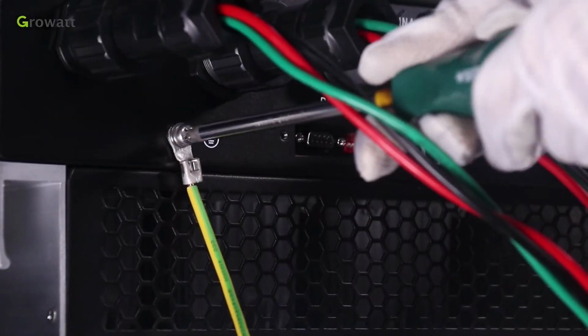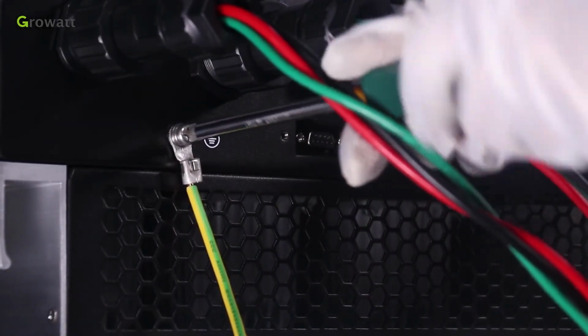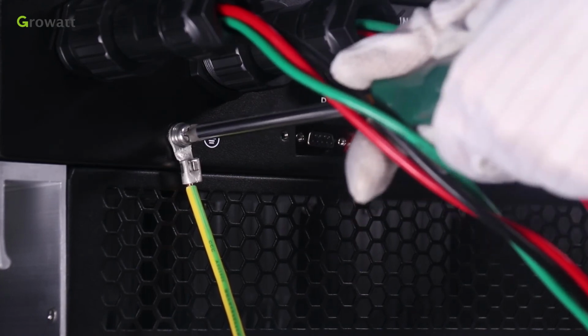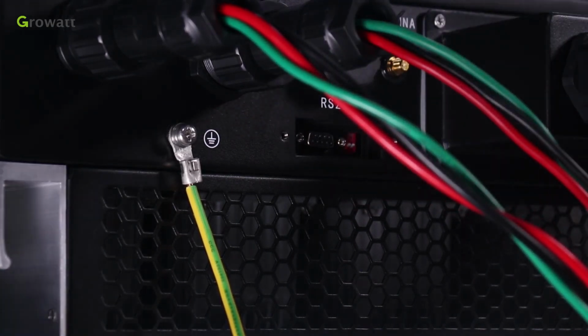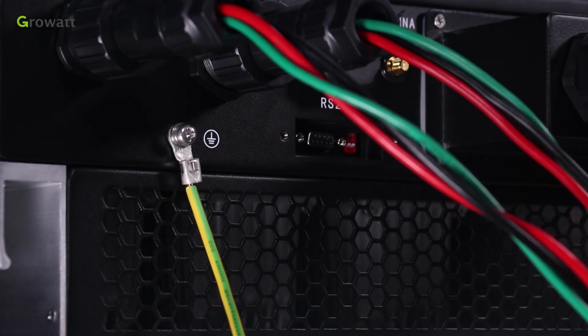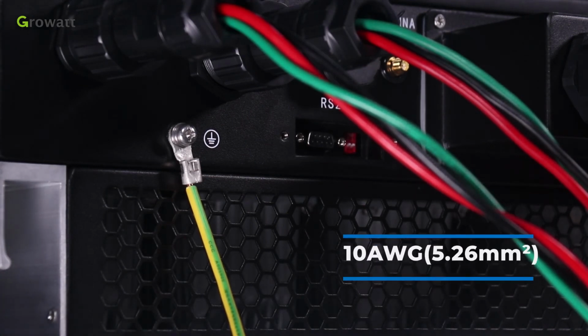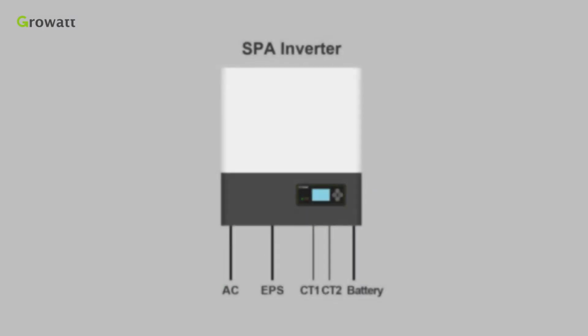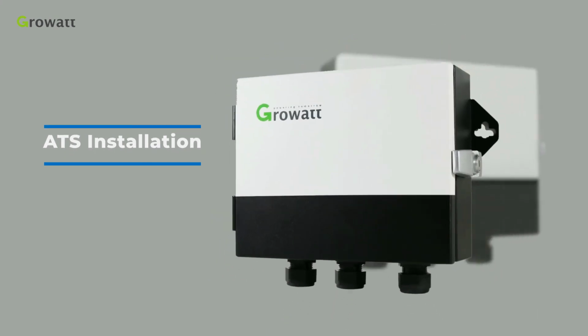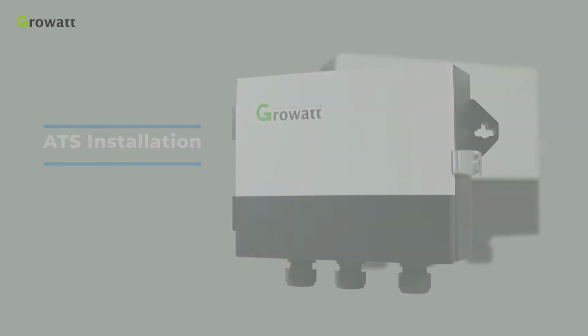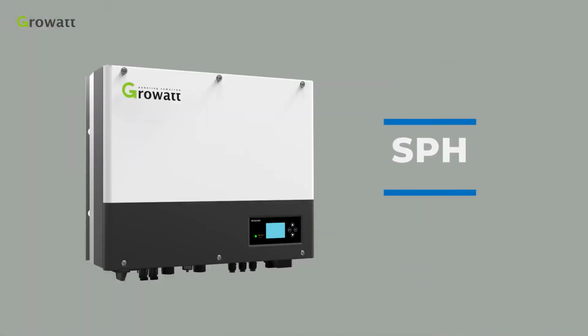Grounding connection. SPA series must be grounded by cable. The grounding point is shown as follows, and the minimum grounding cable wire diameter is 10 AWG, 5.26 square millimeters. In the SPA system, the EPS terminal can't connect to grid. If you want to use on-grid and off-grid together, you can use an ATS, Automatic Transfer Switch device. For the details of ATS installation, please refer to the SPH video.